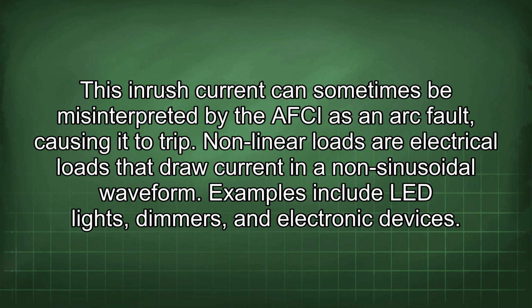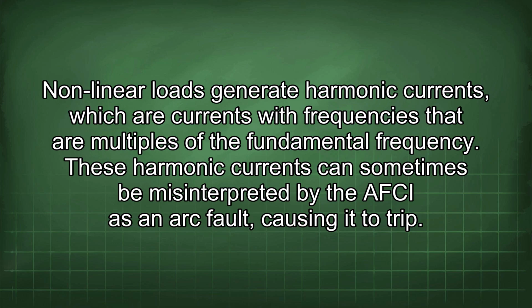Nonlinear loads are electrical loads that draw current in a non-sinusoidal waveform. Examples include LED lights, dimmers, and electronic devices. Nonlinear loads generate harmonic currents, which are currents with frequencies that are multiples of the fundamental frequency. These harmonic currents can sometimes be misinterpreted by the AFCI as an arc fault, causing it to trip.